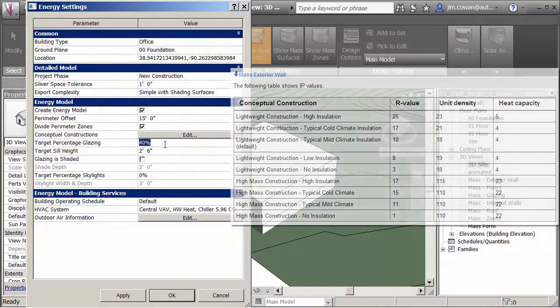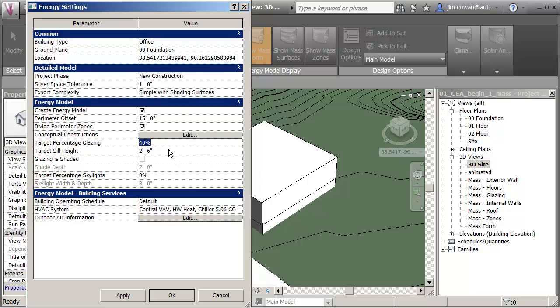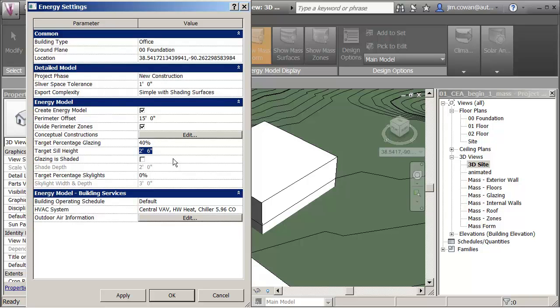Percentage glazing, you can set this to whatever you want. I'm just going to leave it at the default, 40. Sill height, you can set that to any height that you want. If you specified such a high percentage of glazing that it couldn't keep the 2'6" sill height, then it will move the bottom of the glazing down. Is the glazing to be shaded or not? At the moment I'm saying it's not shaded. If I did, I'd be able to choose a shade depth. Percentage skylights, I'm saying none at the moment.